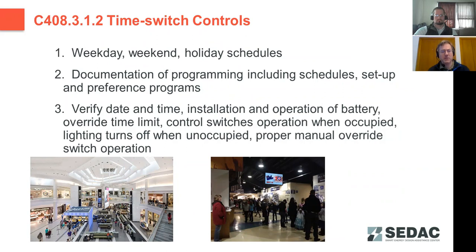An important thing is making sure that there's documentation of the initial schedule and setup, such that in the event the program gets lost, the time switches are required to be able to maintain their memory or their functionality for at least 10 hours after a power failure.